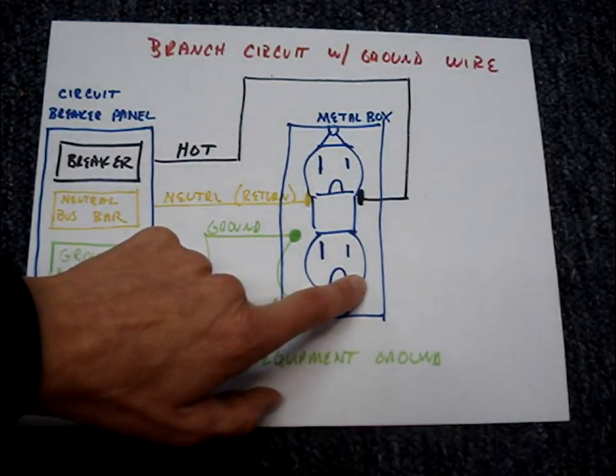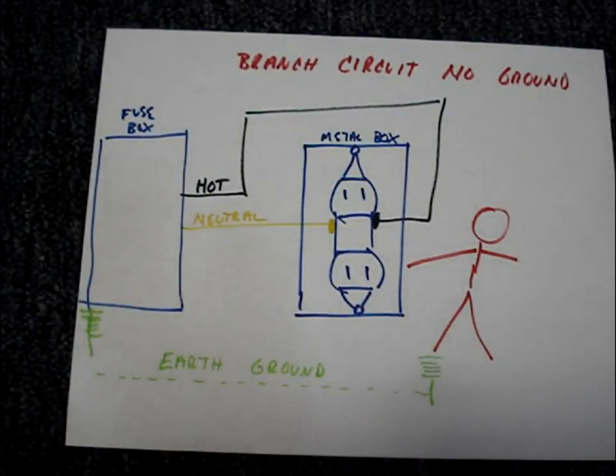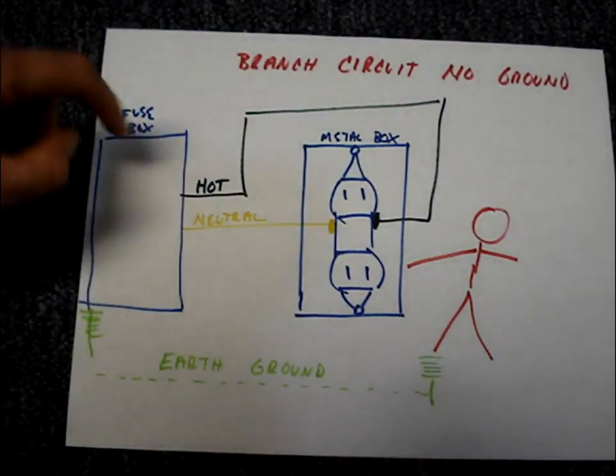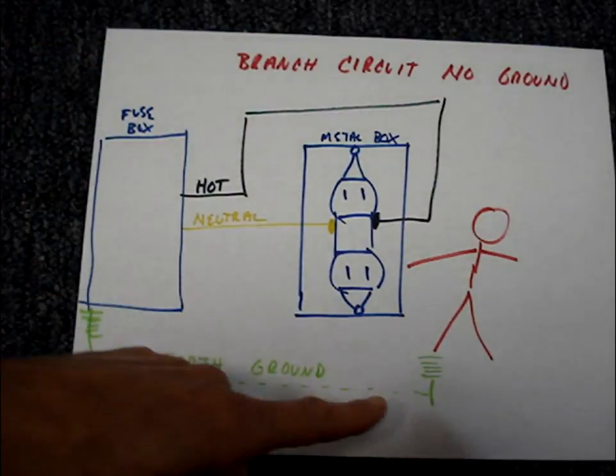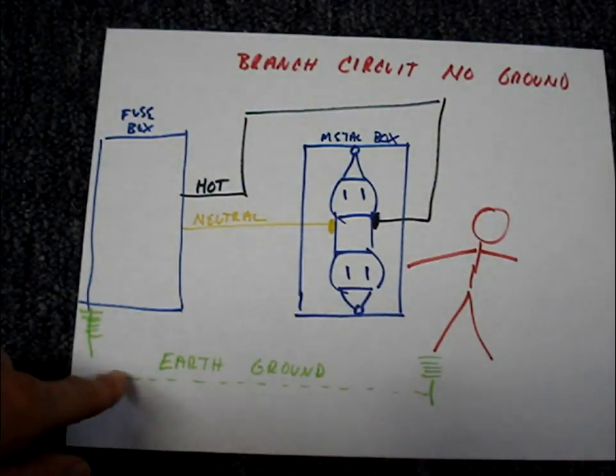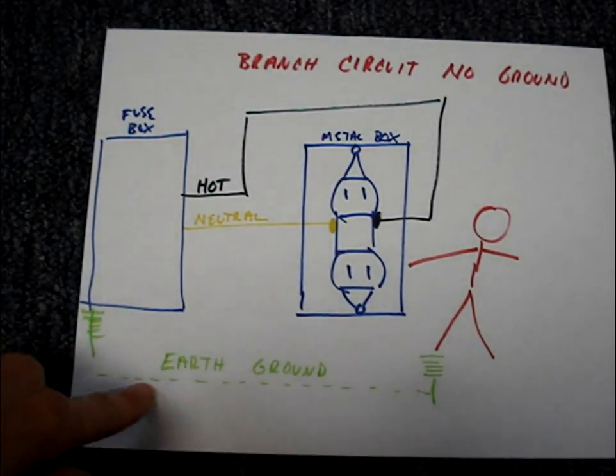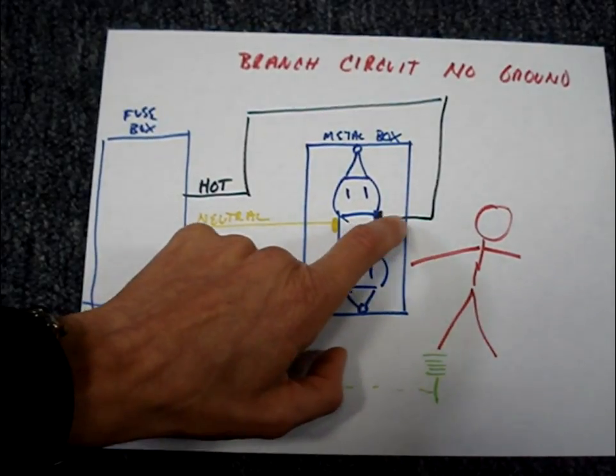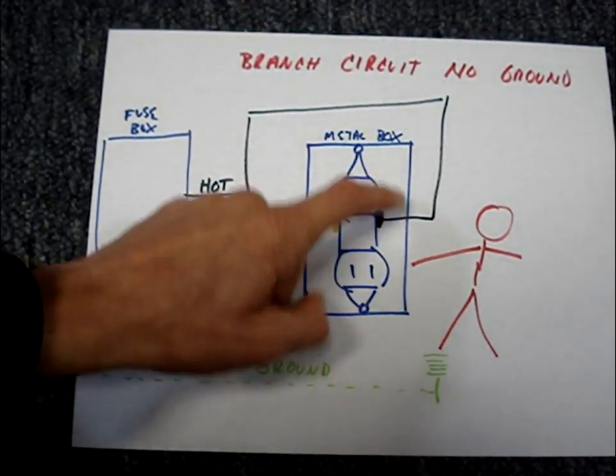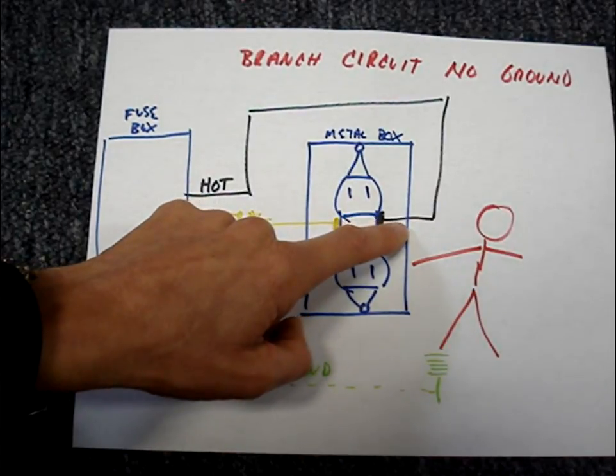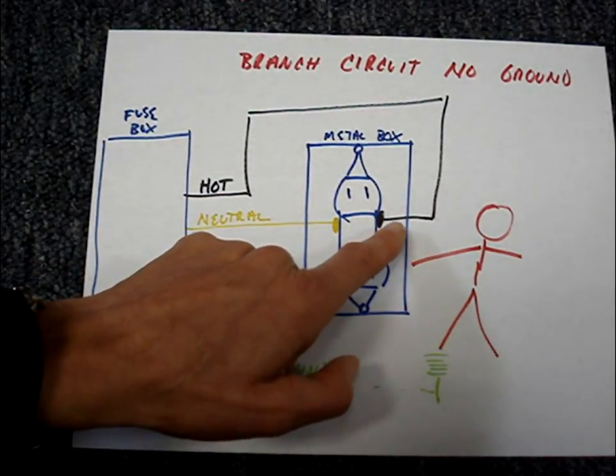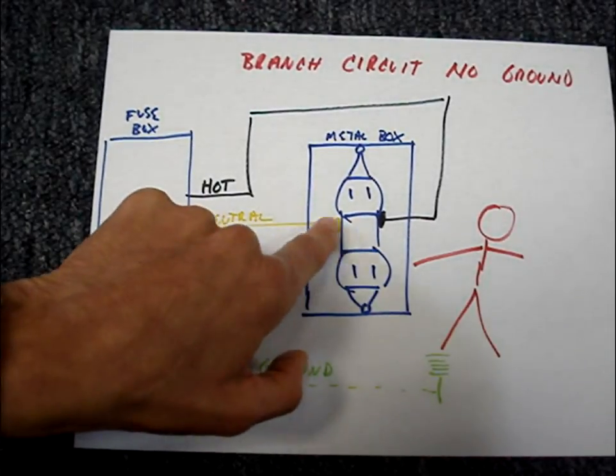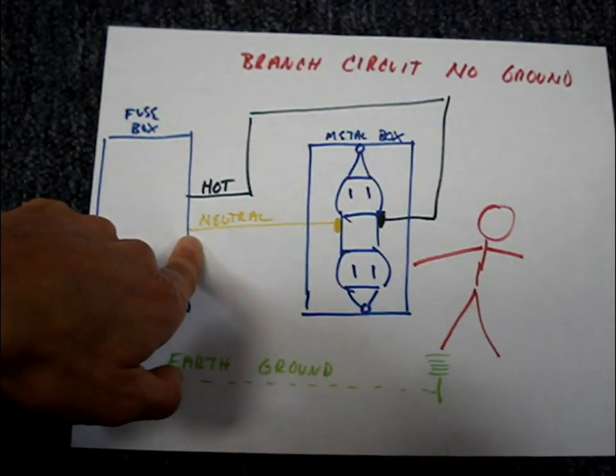So here's a circuit that only has a hot and neutral wire. The earth under the right conditions can act like a wire. If the black hot wire on this circuit made contact with the metal box, it would energize it. It would have no path back to its source because this isn't grounded so it couldn't return on the neutral wire.